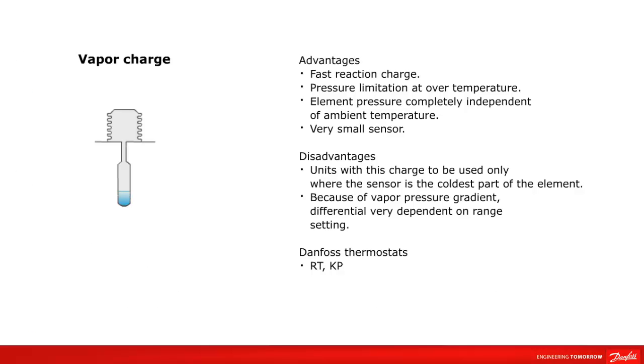The advantages of the vapor charge are fast reaction, pressure limitation at over-temperature, element pressure completely independent of ambient temperature, and very small sensors. The disadvantages are that units with this charge can be used only where the sensor is the coldest part of the element, and that the differential is very dependent on the range setting because of vapor pressure gradient.